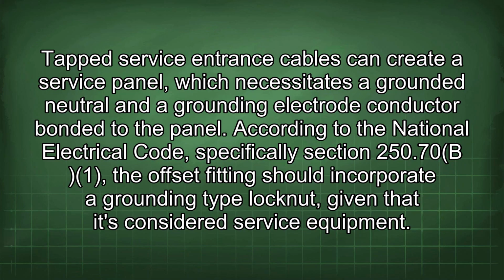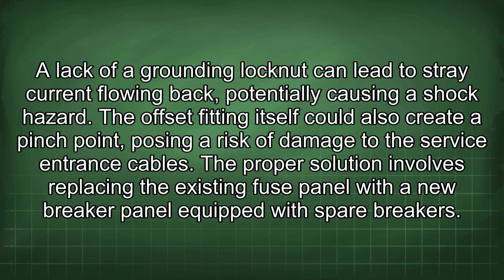Tapped service entrance cables can create a service panel, which necessitates a grounded neutral and a grounding electrode conductor bonded to the panel. According to the National Electrical Code, specifically Section 250.70, the offset fitting should incorporate a grounding type locknut, given that it's considered service equipment. A lack of a grounding locknut can lead to stray current flowing back, potentially causing a shock hazard. The offset fitting itself could also create a pinch point, posing a risk of damage to the service entrance cables.